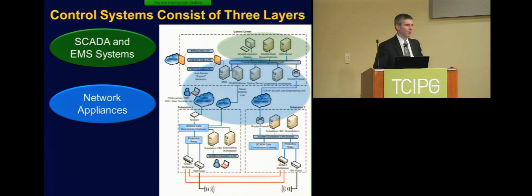They can do that through various mechanisms. If it's a legacy system, like substation 1 shown on the left, we'll refer to it as a serial substation - it'll have modems set up into it. On the right is a more modern, Ethernet-based substation. So we have lots of varying types of communication coming in and out of substations, certainly based on the age of the substation.